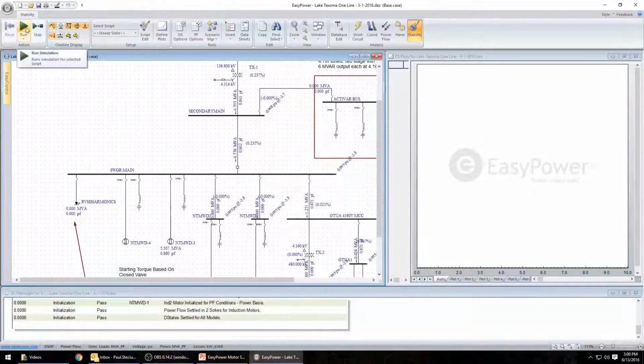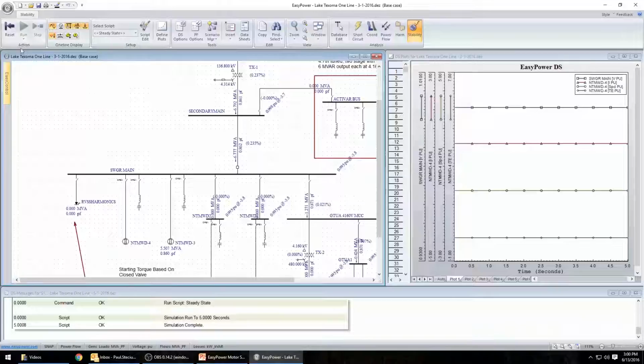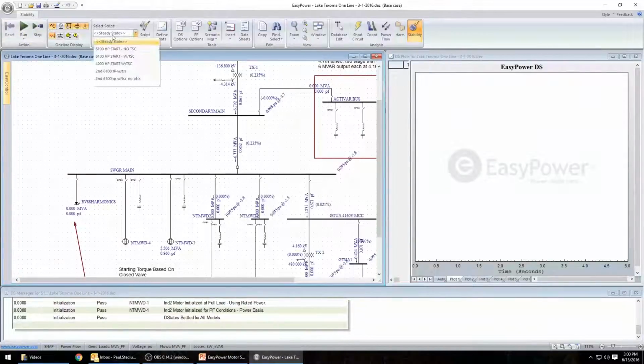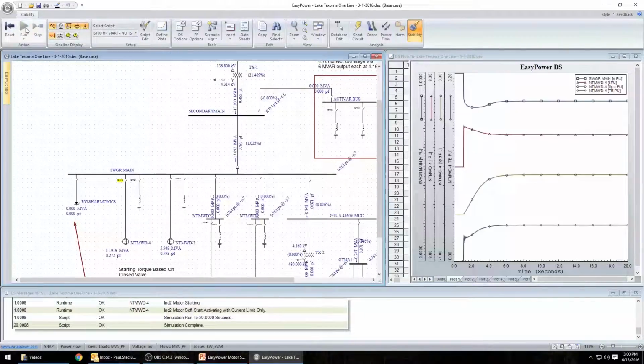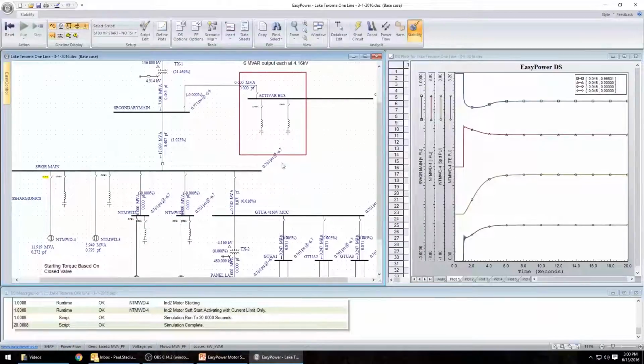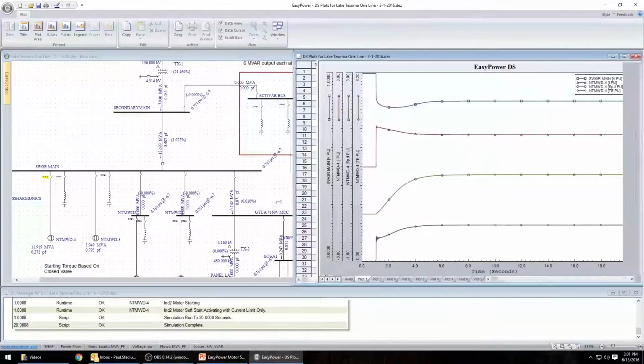So I run the simulation. No, I didn't get that. Sorry about that. It's a no TSC start. We want to run that script. Hit run. And you can see here, the first thing you can note is that the per unit voltage is 0.761 per unit, and that's because the motor did not start. It's in a locked rotor condition at this point. The graph over here shows what is going on.